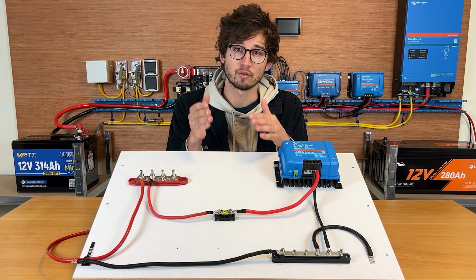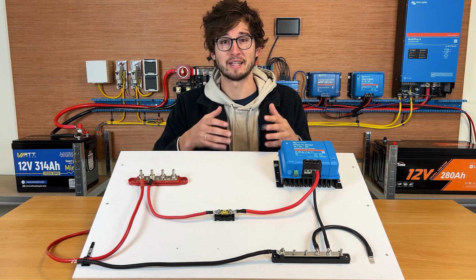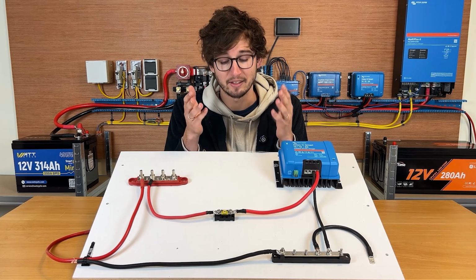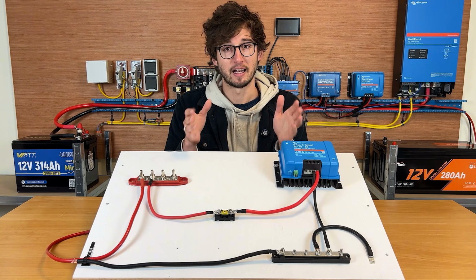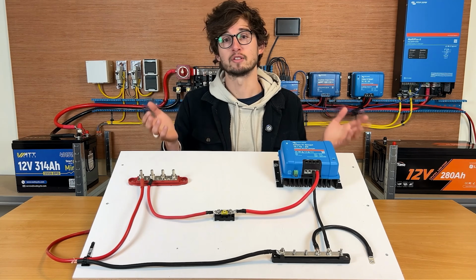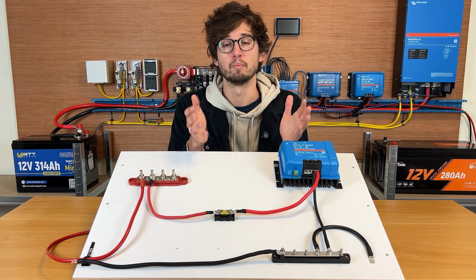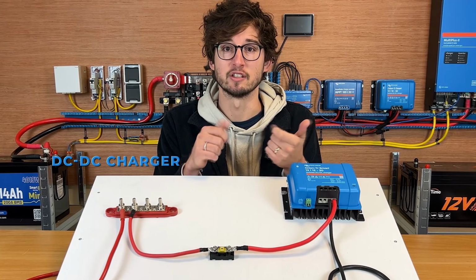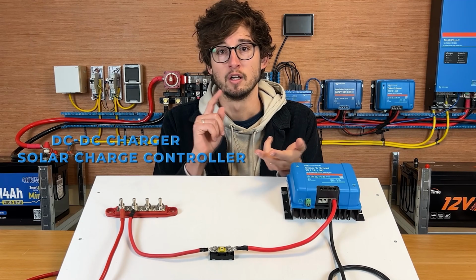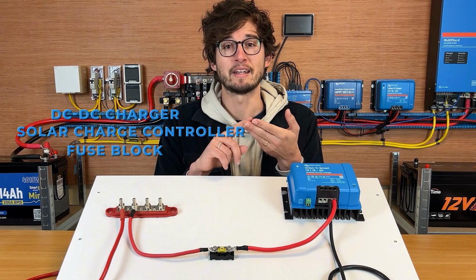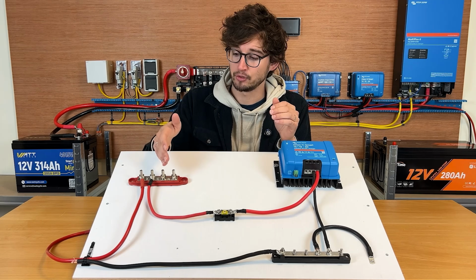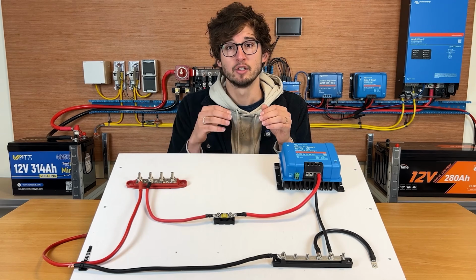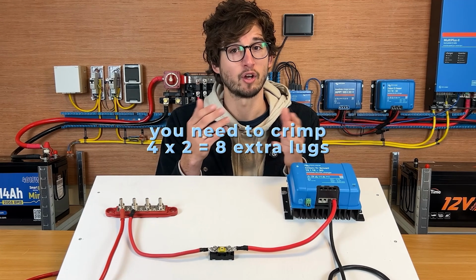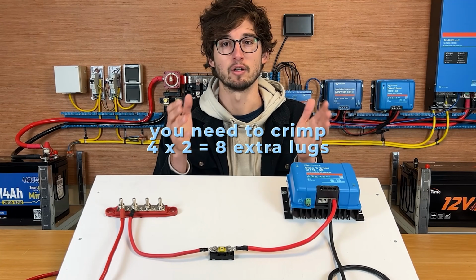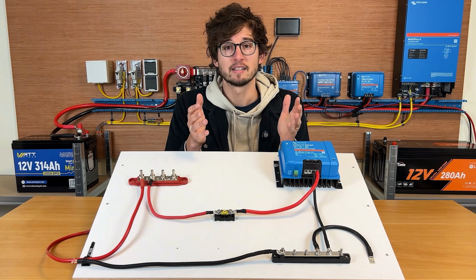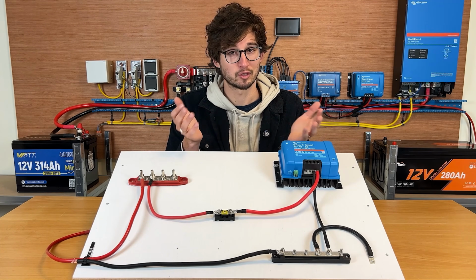So each extra lug you have to place is an extra opportunity to create a failure. A basic electrical installation most of the time has at least 4 electrical components, like a DC-DC charger, a solar charge controller, a 12-volt fuse box and an inverter. That means when you use an individual bus bar like this, you need to crimp 4 times 2, which is 8 extra lugs. So that gives you 8 extra failure points, so to say.